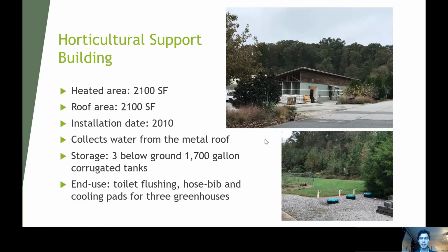So the next system I will be discussing is the horticultural support building. This was installed in 2010, the same time as the construction of the building. It collects water from the metal roof, and the water is stored in 3 below-ground 1,700-gallon corrugated tanks. Water is supplied for 3 end uses: some toilet flushing in the building, a hose bib, and cooling pads in the 3 adjacent greenhouses.